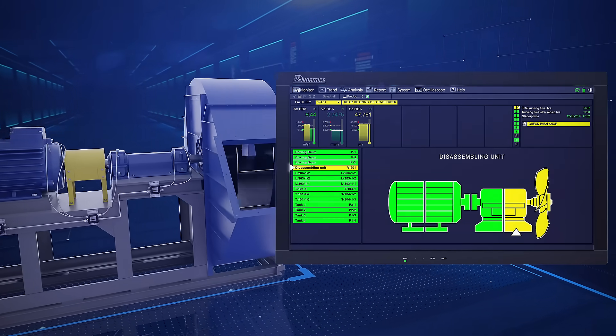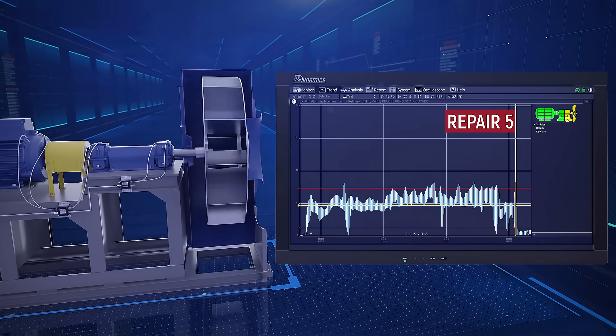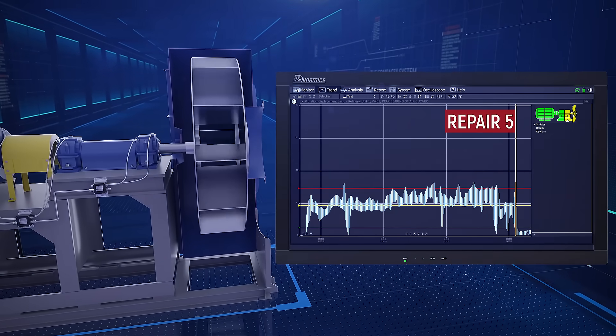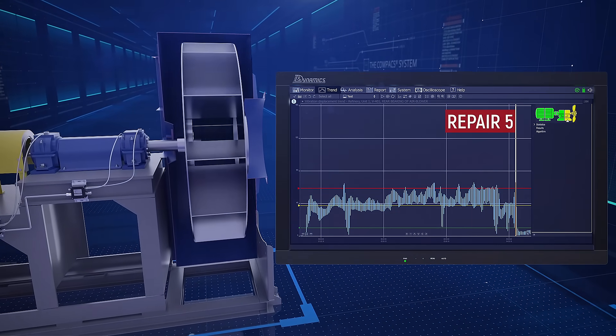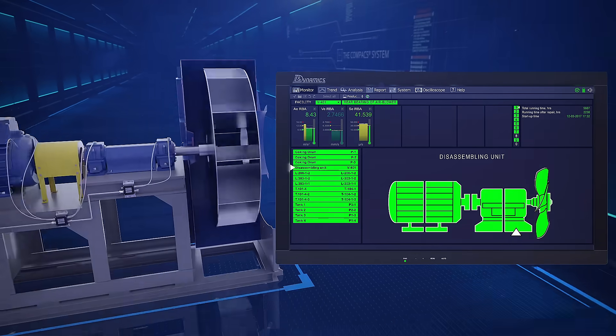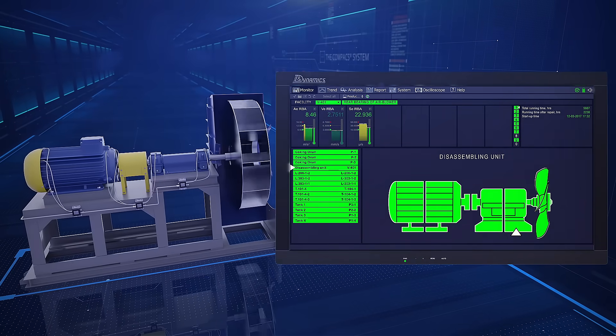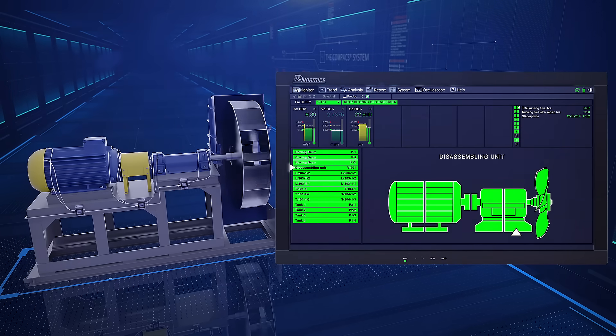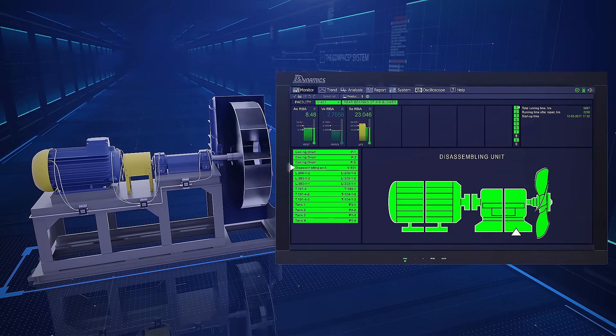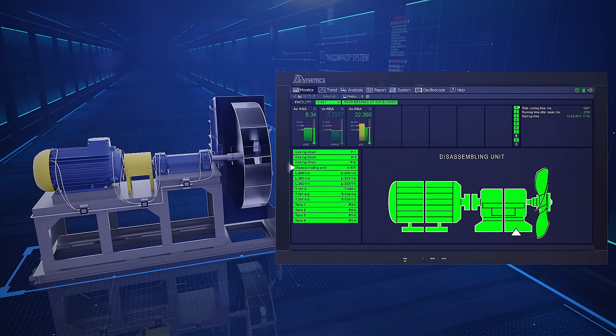At point five, the impeller was dynamically balanced and the health improved considerably. It also moved to an acceptable state and its vibration decreased significantly. The root cause of the exhaustor's failure was impeller imbalance.